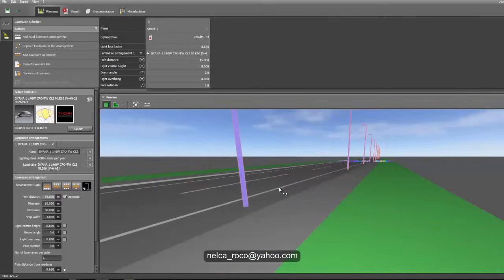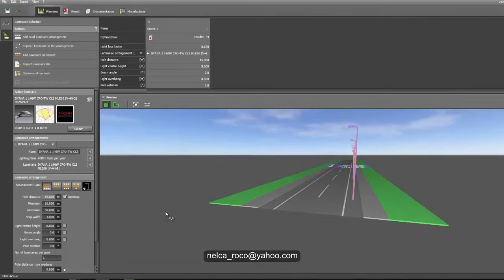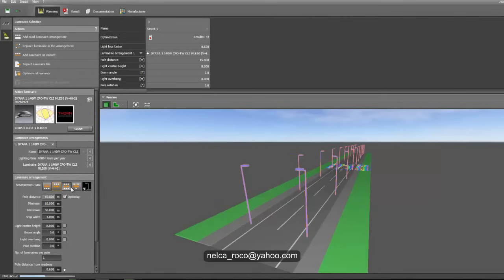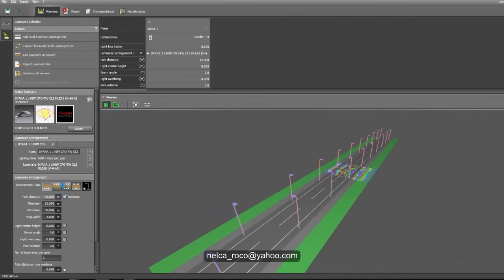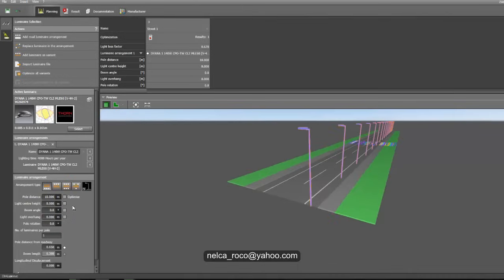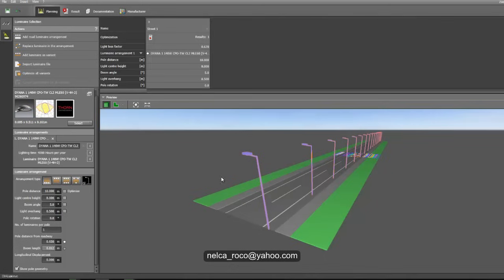Let's configure the arrangement — we can do both sides, one side, or alternate. Since he didn't specify, we'll use one side. Uncheck optimize, set spacing to 10 meters, boom angle to 5 degrees, and overhang to 0.5 meters. As soon as I change the parameters here you can see the 3D file updating accordingly. Pole rotation stays the same, luminaires per pole set to 1.